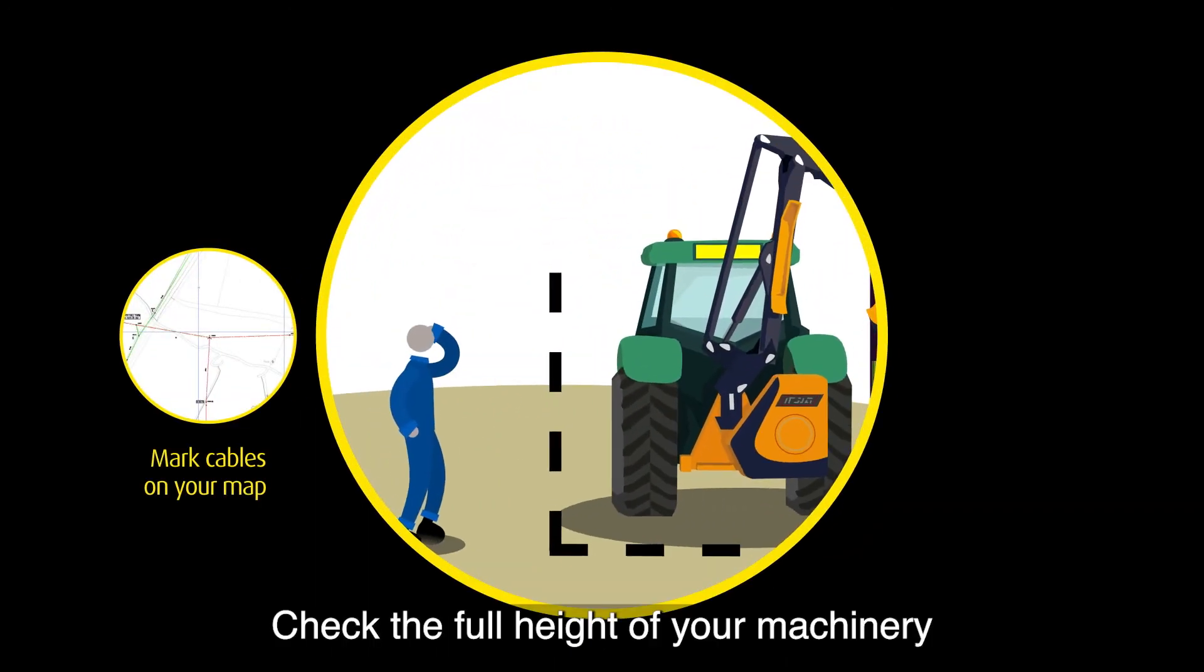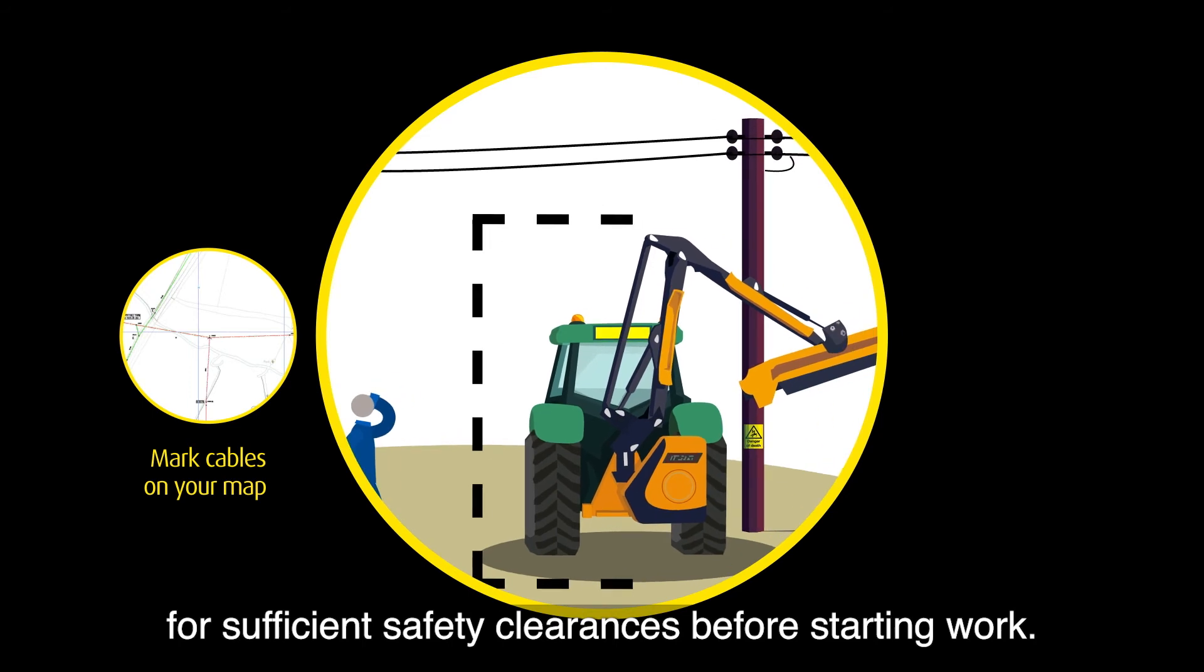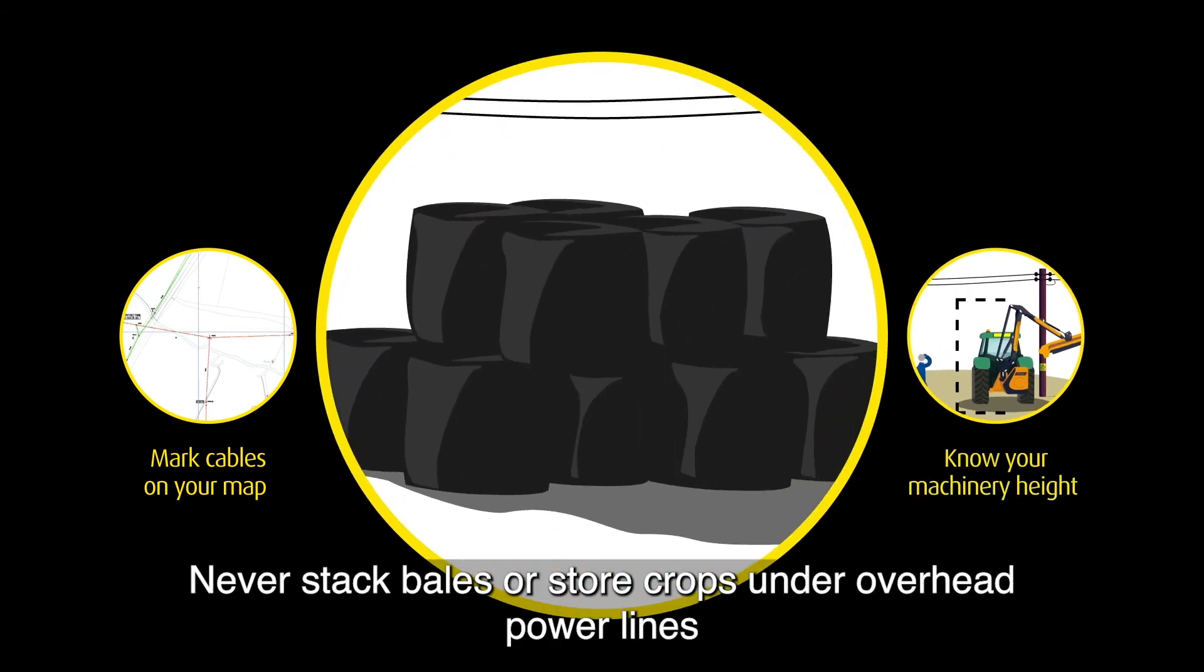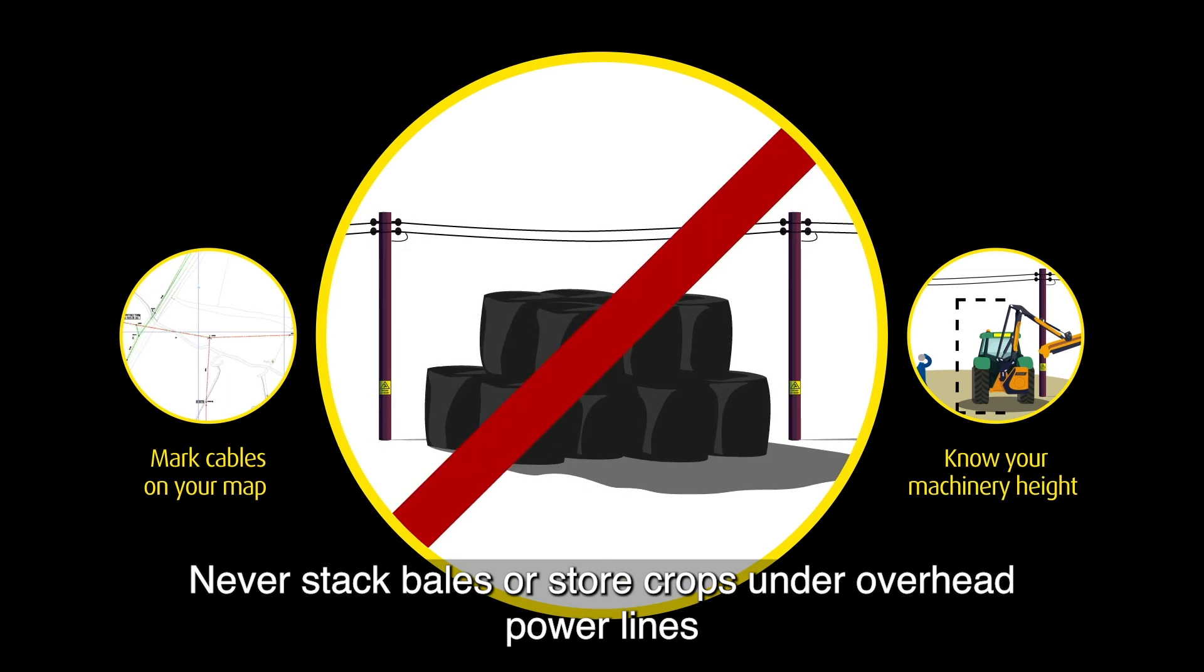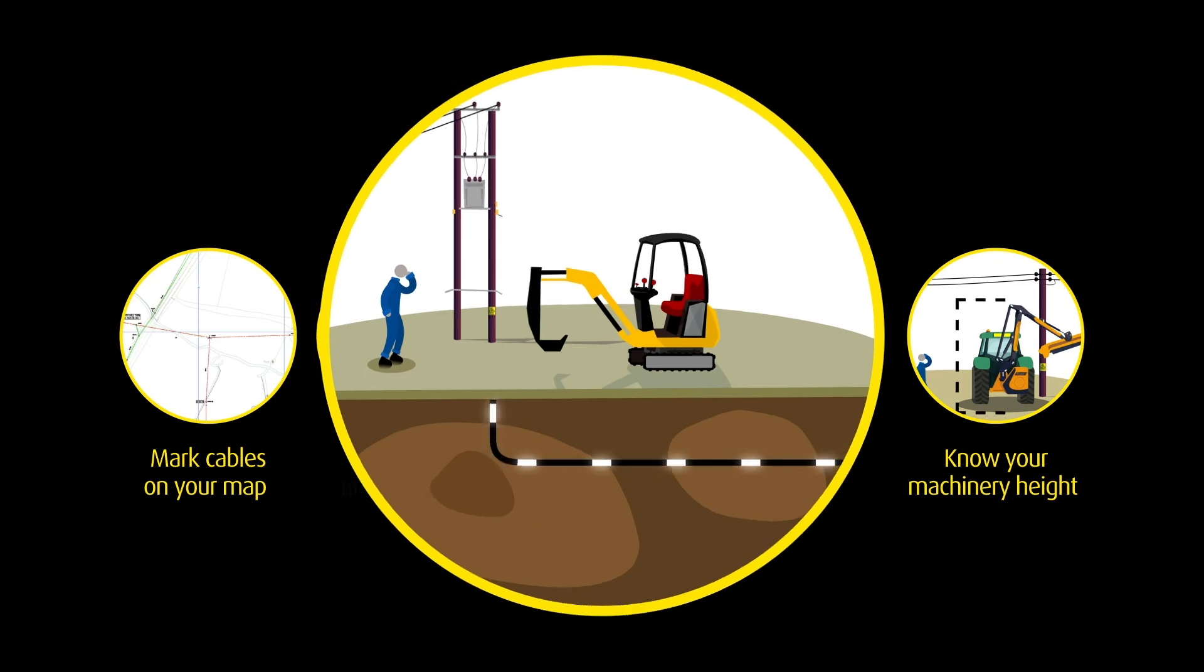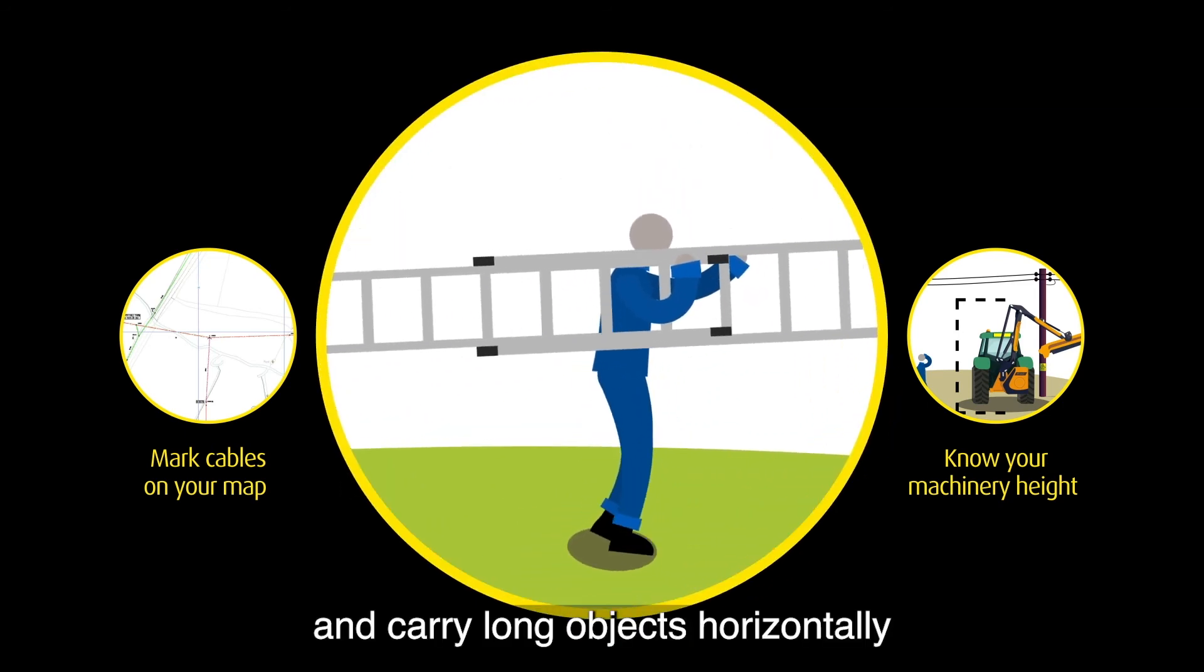Check the full height of your machinery for sufficient safety clearances before starting work. Never stack bales or store crops under overhead power lines. Check for cables before you dig and carry long objects horizontally.